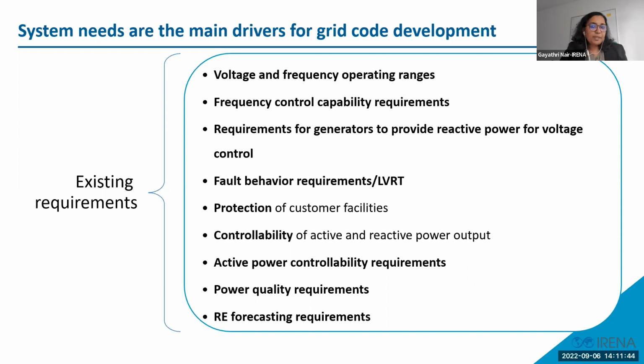On providing reactive power support and voltage control, there are two aspects to this. One is to provide reactive support from the generator itself, and the other is to have the capability to implement different control strategies like power factor correction or constant power factor control. These are visible in almost all transmission and sub-transmission grid codes and also in distribution grid codes worldwide.